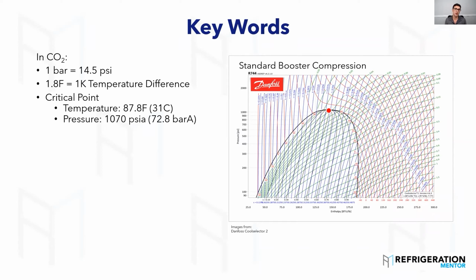In Quebec, one province here in Canada, anything over 50 kilowatts, which is 67 horsepower, which is not a big rack, needs to be below 150 GWP, and that's pretty much CO2. California's got a lot of regulations. They got an alliance there, so you need to understand this. A little bit off topic there. So transcritical is anywhere above that point. We talked about that critical point. So anything above here, when we get up here, is the transcritical zone.